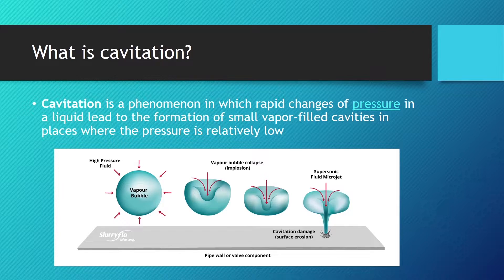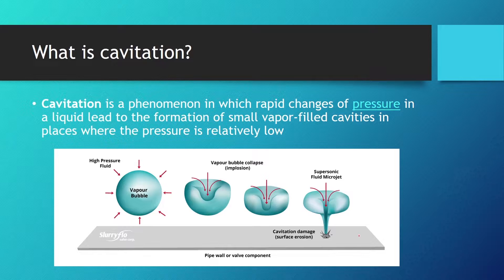High vacuum creates vapor bubbles within the oil which are carried to the discharge pressure side of the pump, and these bubbles collapse in this fashion and create a supersonic fluid microjet that damages the inner components of our pump.